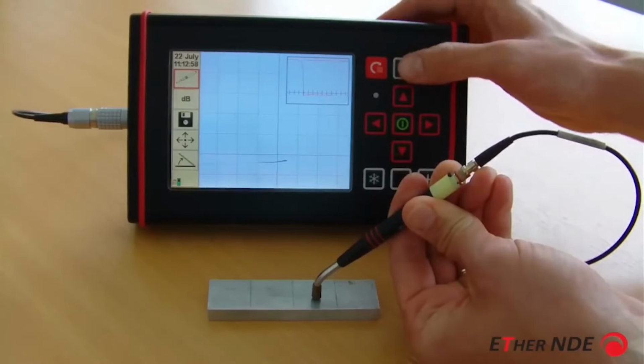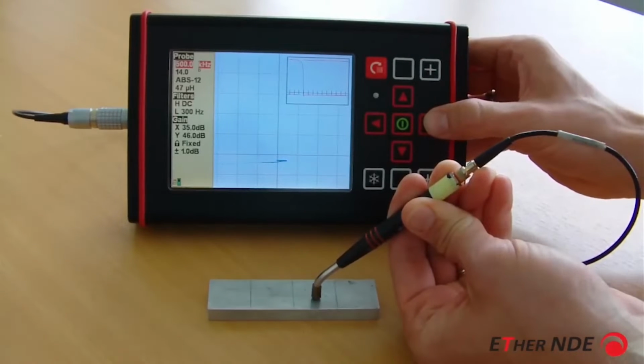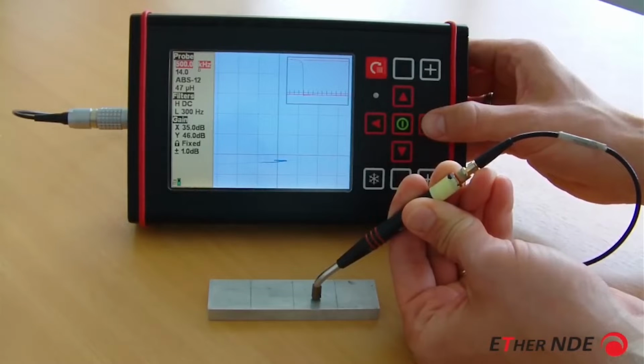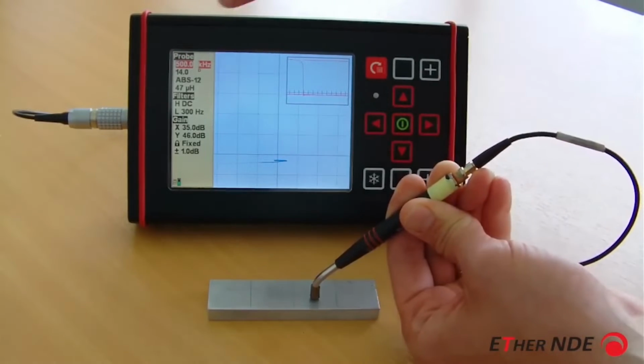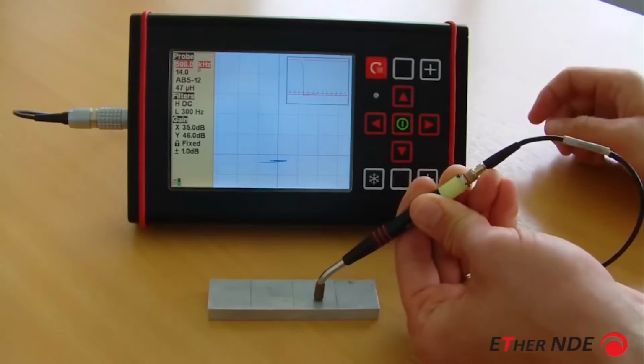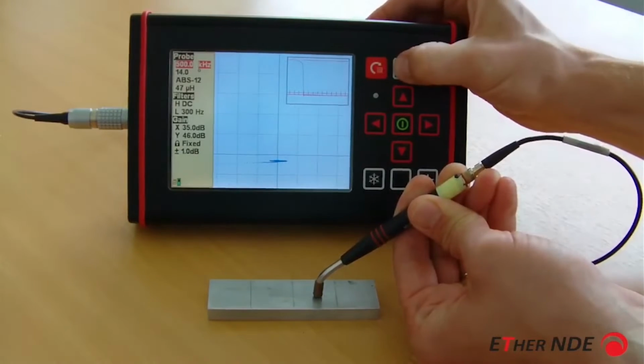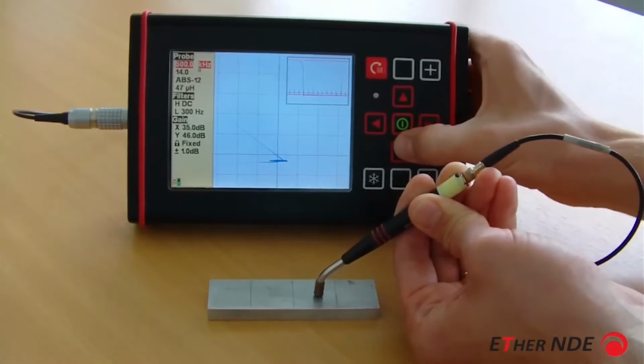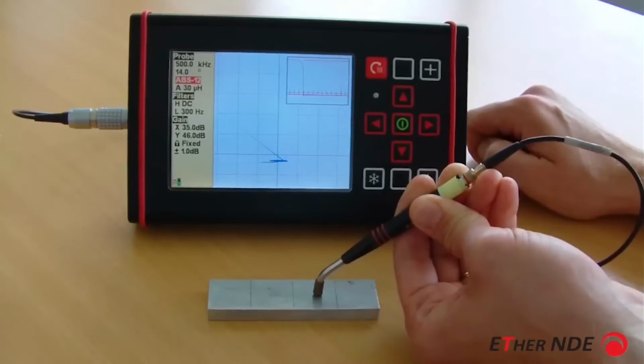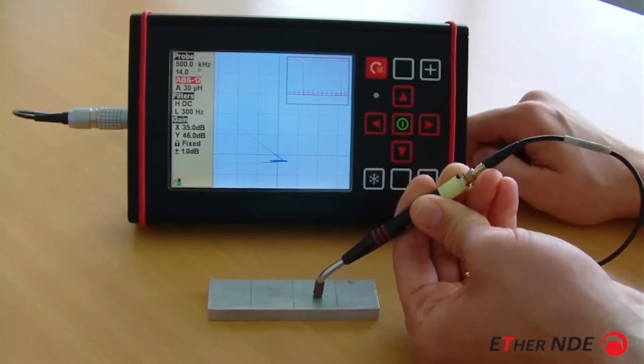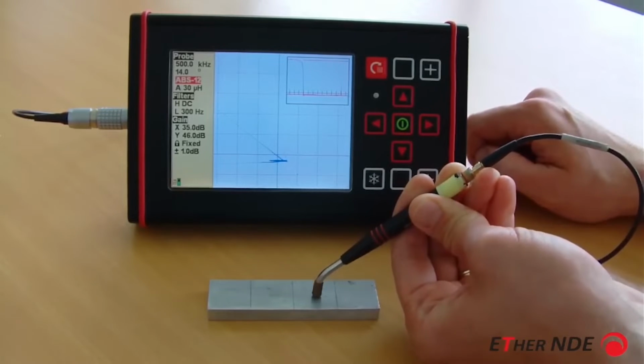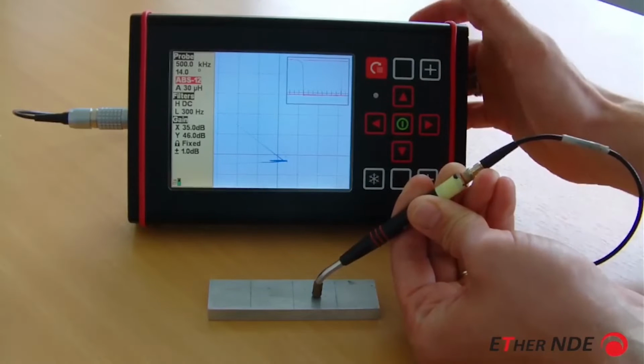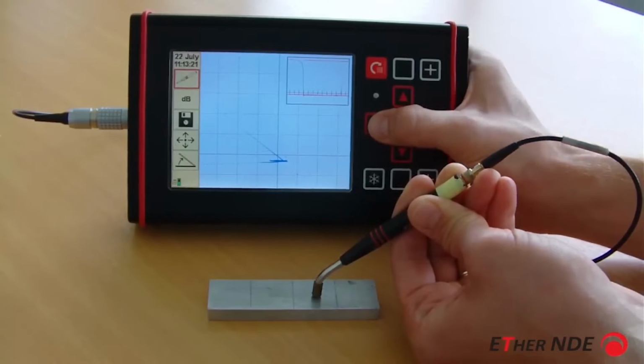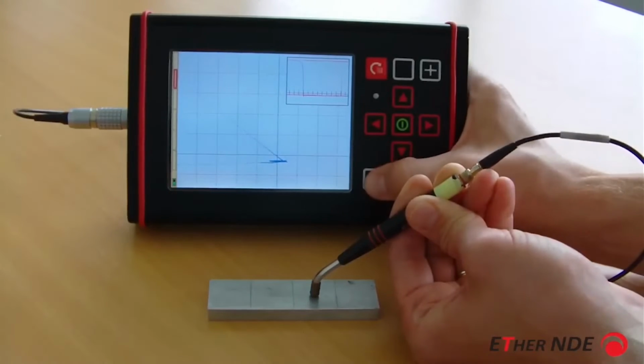do an auto load. See, the load is currently set to 47 microhenries, as you can see just there. So I should do an auto load, and it's now set to 30 microhenries. So again, it has improved the load setting, so the probe should be more sensitive.